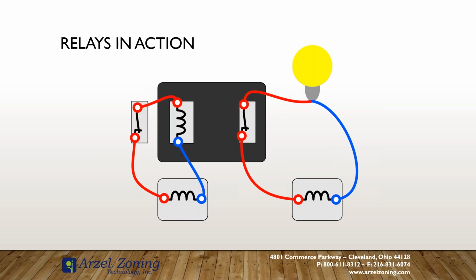light. In our building here at Arzel, we actually have a lot of low voltage light switches. That was a common thing in some commercial buildings long time ago. Not so much today, but it used to be that way, so that if somebody were to damage the switch, there wasn't a dangerous high voltage there. So what they did is they would have a relay panel somewhere in the building, and it can really look confusing when you first see it, but that relay panel switches with these 24 volt switches that are all over the walls in our building. And as you hit the switch, it's a 24 volt switch that then energizes the relay, and that relay allows the lights to come on. So we have a low voltage controlling a high voltage, and that's what relays are doing for us in that instance.